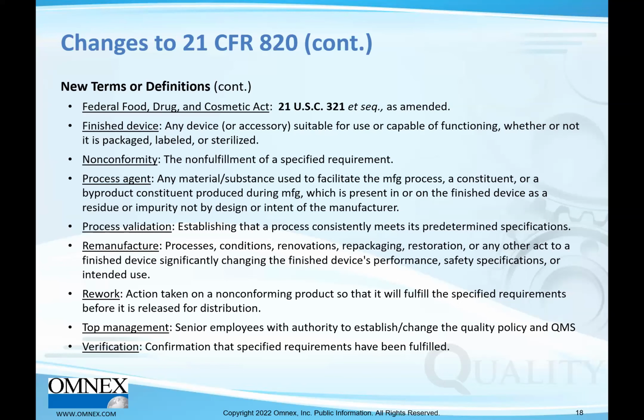Nonconformity, the non-fulfillment of a specified requirement. Process agents are any materials, substances used to facilitate the manufacturing process. A constituent or a byproduct constituent produced during manufacture, which is present in or on the finished device as a residue or impurity, not by design or intent of the manufacturer. So it's not intended to be a product, part of the product, but it may be just a result of your processes. Like mold release, if it's used on any molded parts. Process validation is establishing that a process consistently meets its predetermined specs.